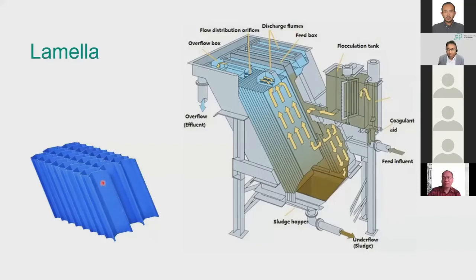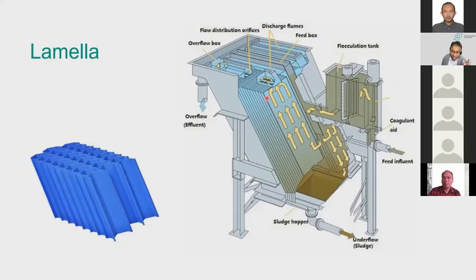Commercial systems such as the Super Pulsator from Suez use tube flocculators and lamella-type plates. While lamella systems have many advantages — reducing sedimentation tank volume and area by 2 to 5 times — there is a disadvantage: cleaning is difficult when plates are spaced only 10 cm apart over a height of 1–2 meters, compared to a standard open tank where anyone can enter and clean it.